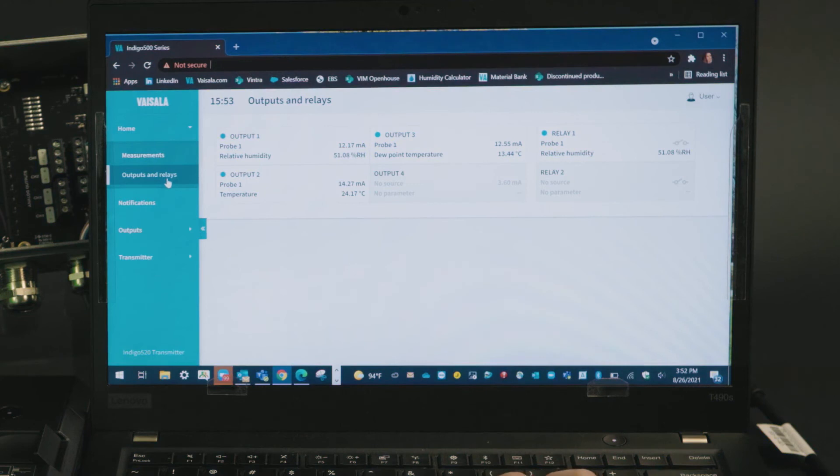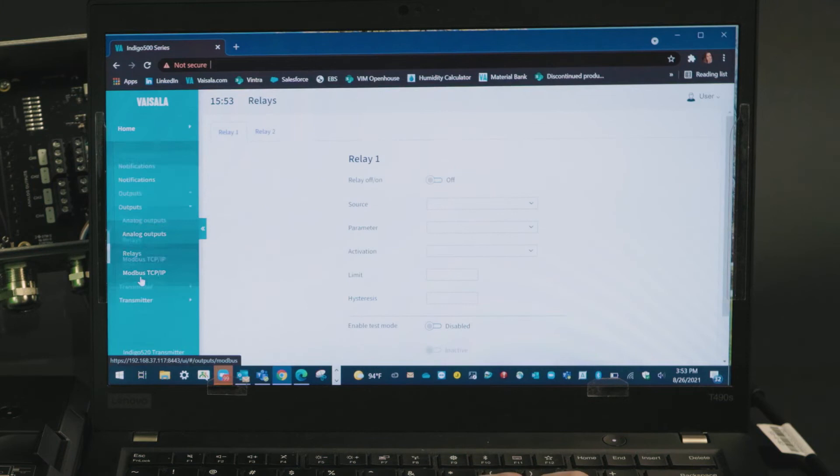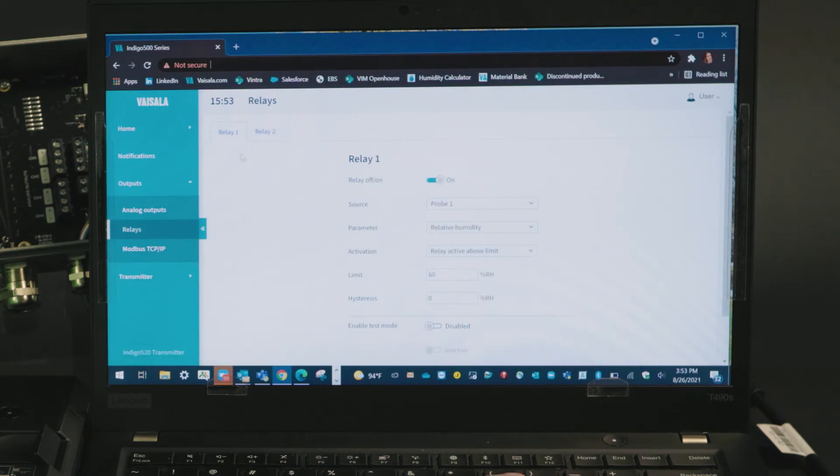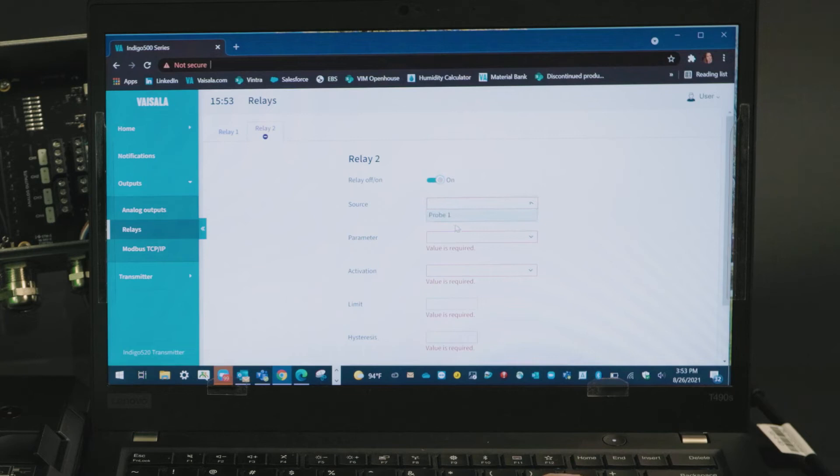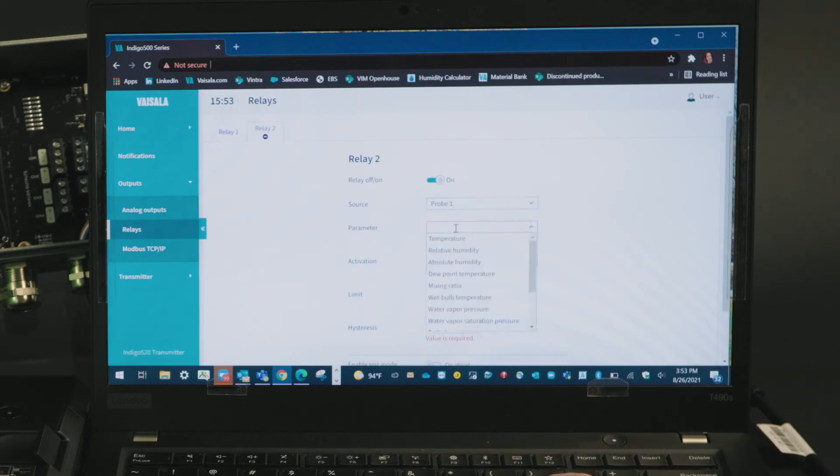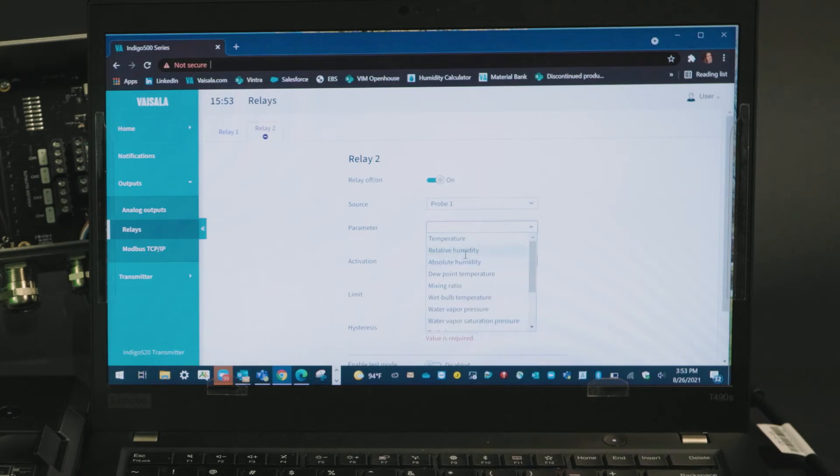Relays will work similarly. Let's dive in, go to outputs relays. As you can see I have one on but we'll move over here and set up another relay. Toggle on, select your probe source, select your parameter. Let's say we want an alarm at 90% humidity.